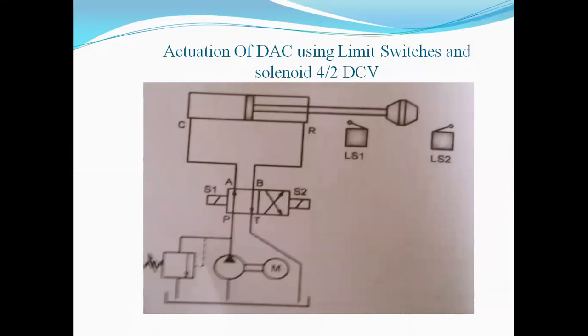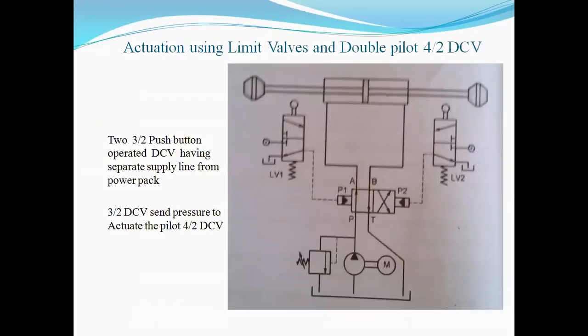Once we place the flow control valve, you can control the supply or the speed of hydraulic oil, and from that you can control the speed of the actuator also. Okay. So a similar circuit by using pressure line. Again in that case we use the roller operated, pilot operated 3/2 direction control valve, which is used by using another power pack unit.